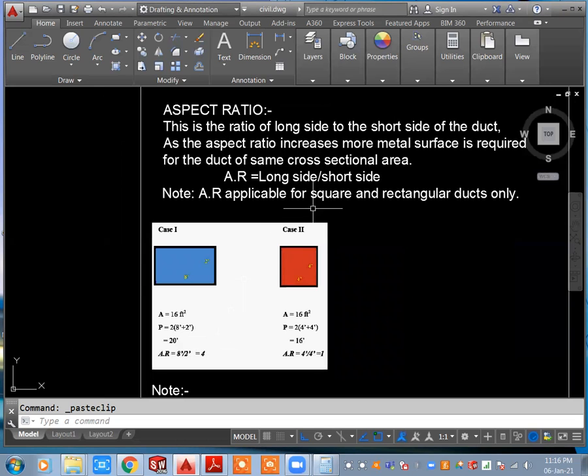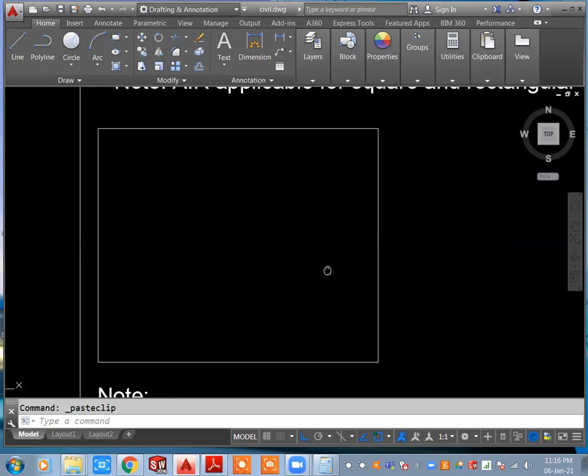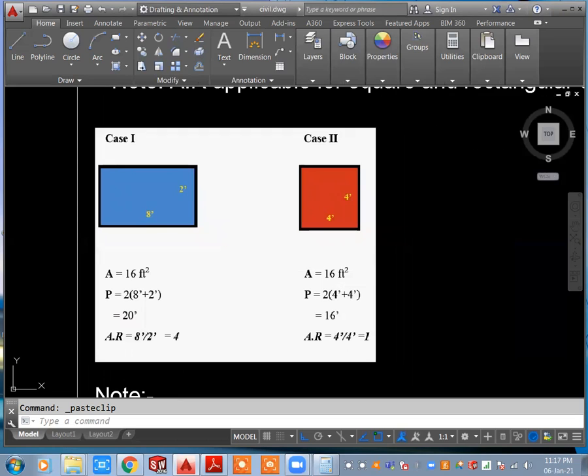The aspect ratio formula is AR = long side ÷ short side. For the rectangular duct (8 by 2), AR = 8 ÷ 2 = 4. For the square duct (4 by 4), AR = 1 — a perfect aspect ratio. For cost balancing purposes, always prefer the aspect ratio equal to or less than 4, or as close to square as possible. Maintaining AR between 1 and 4 helps control cost.